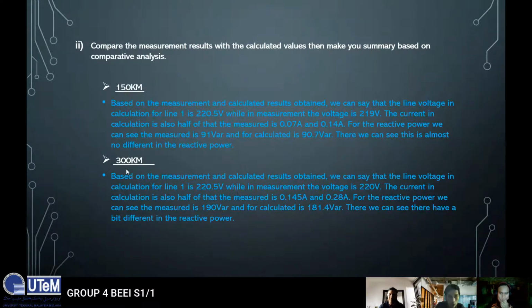Okay, for 300 km, based on the measurement and calculated result obtained, we can say that the line voltage in calculation for line 1 is 220.5 volt, while in measurement the voltage is 220 volt. The current in calculation is also half of the measure: the measured is 0.28 ampere, and the calculated is 0.145 ampere. For the reactive power, the measured is 190 var, and the calculated is 181.4 var. There we can see they have a bit of difference in the reactive power.